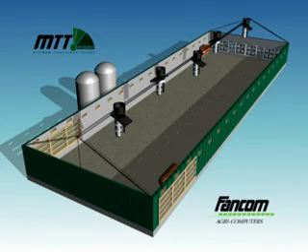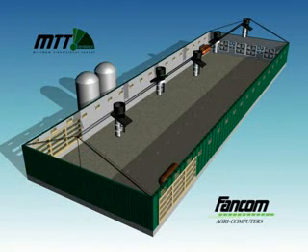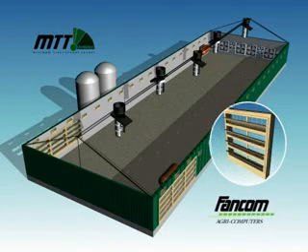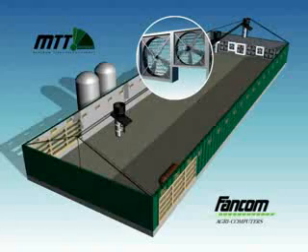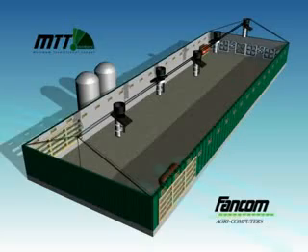The final phase of the MTT concept is tunnel ventilation, which exhausts the heat produced by the birds. The air inlets are fully closed and the tunnel inlets are opened as required. The large fans in the rear wall are activated one by one, creating the so-called tunnel effect, where air flows over the animals at great speed.